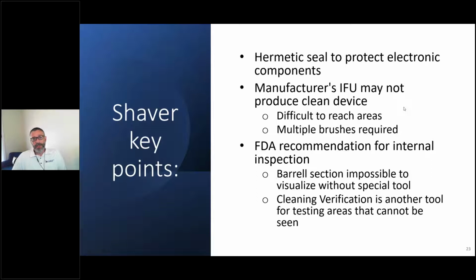Also, as Jahan mentioned, what's a bit of a problem with these is that the IFUs may not render a clean device, and that's tough because we rely on them. We've been asking for decades now: give me the IFU, please don't bring something into my facility without one. The IFU comes, you follow it, and yet you find there are very difficult to reach areas, and multiple brushes are really required if you ever have any chance of getting this clean. Even meticulously following an IFU doesn't necessarily result in a clean device.